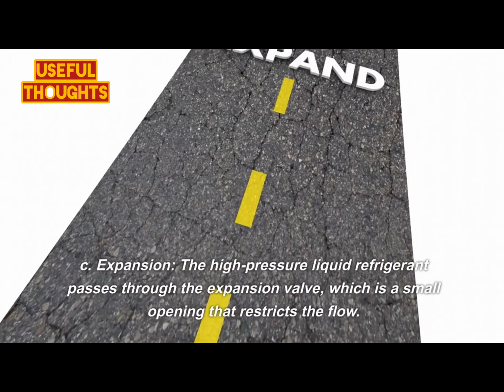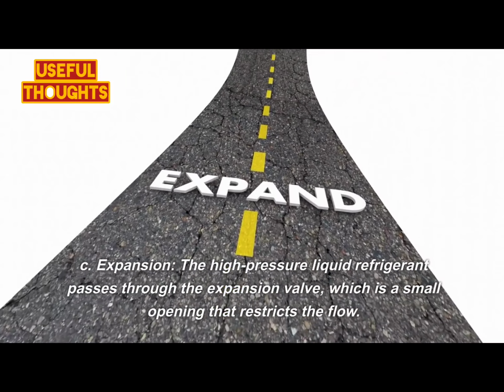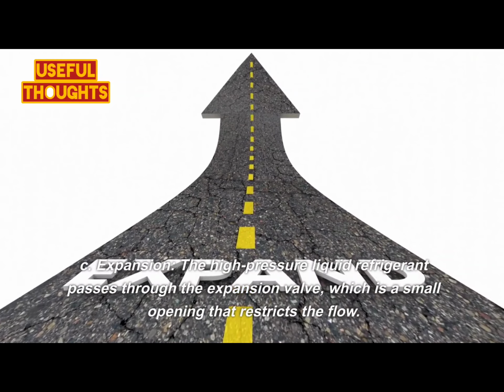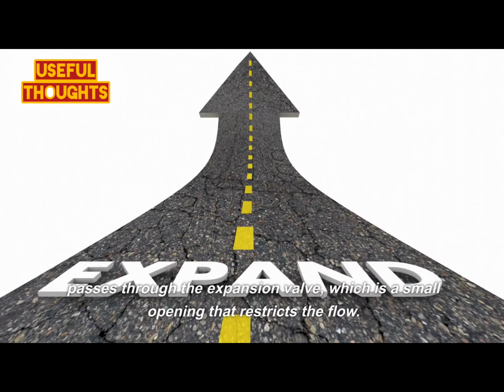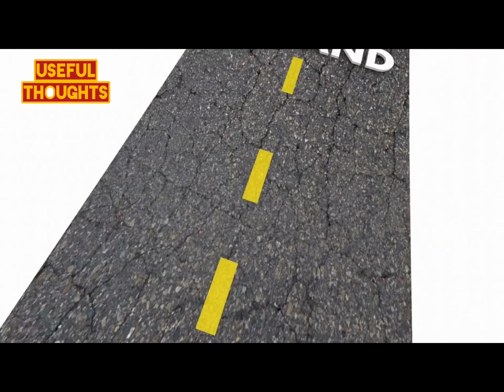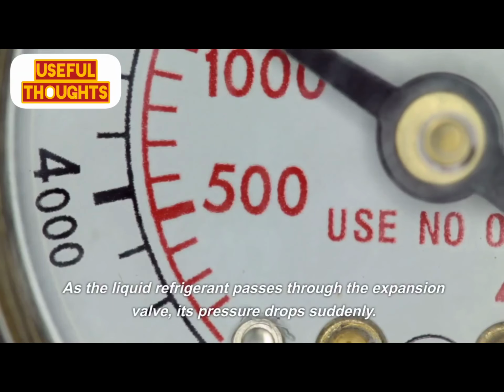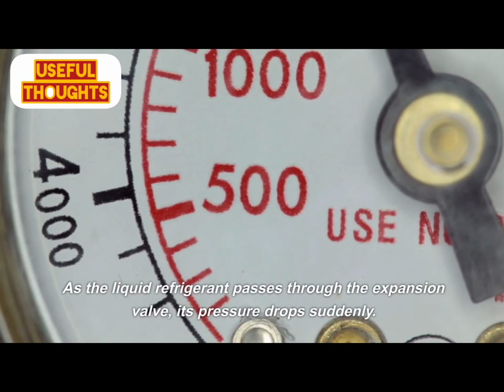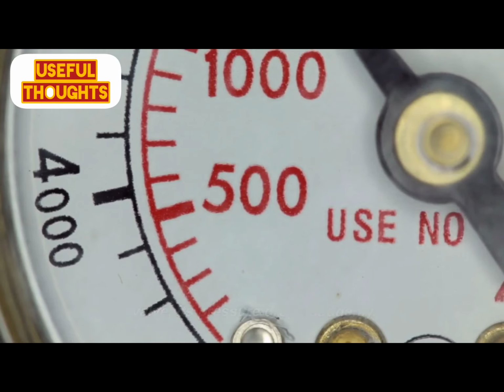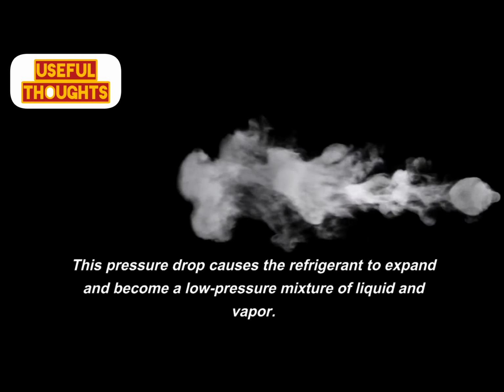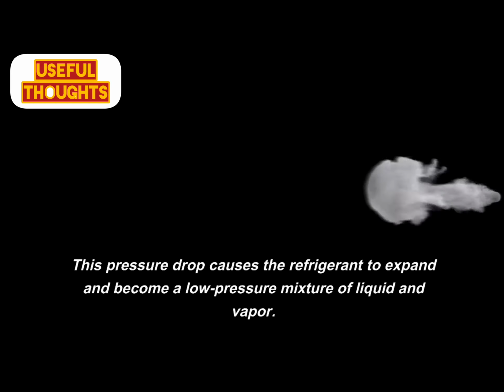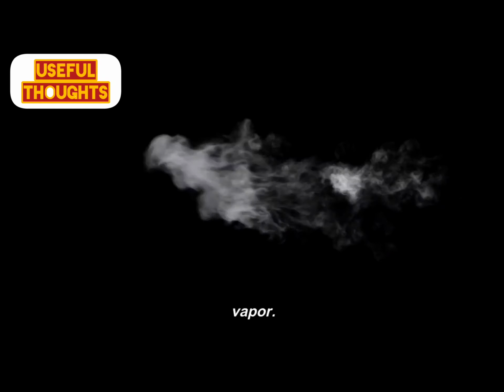C. Expansion. The high-pressure liquid refrigerant passes through the expansion valve, which is a small opening that restricts the flow. As the liquid refrigerant passes through the expansion valve, its pressure drops suddenly. This pressure drop causes the refrigerant to expand and become a low-pressure mixture of liquid and vapor.